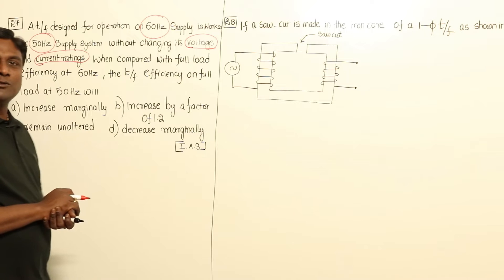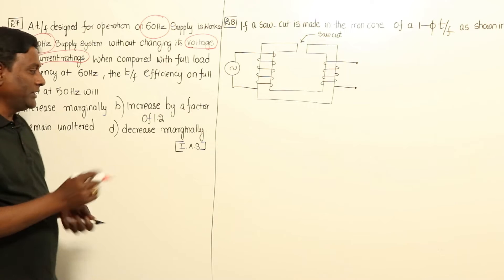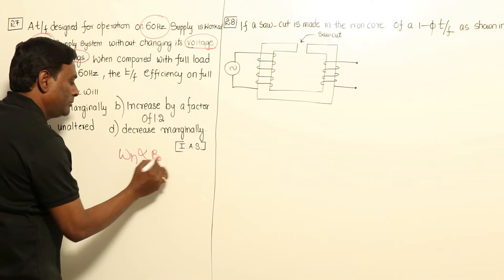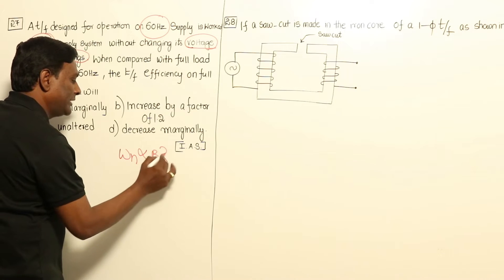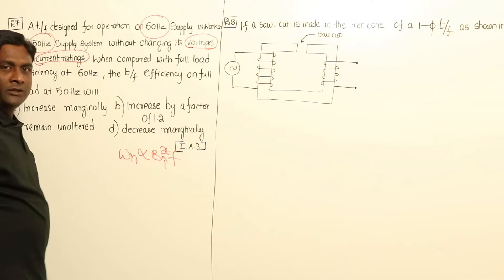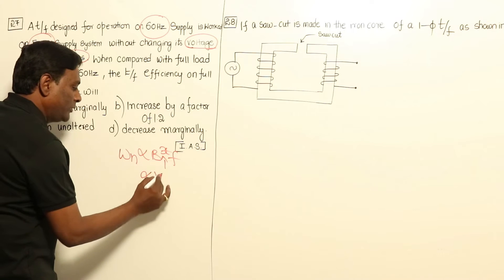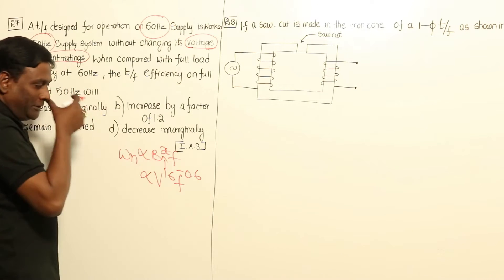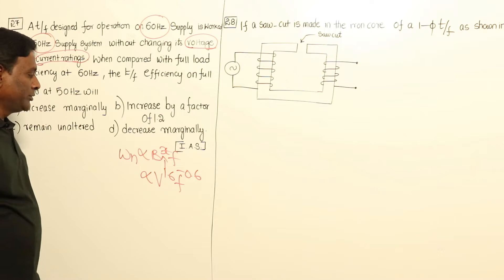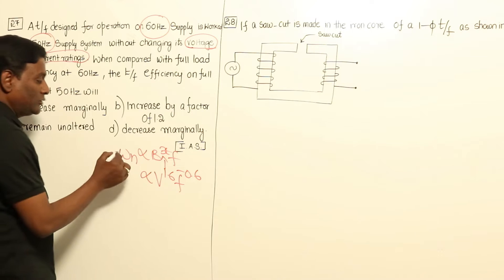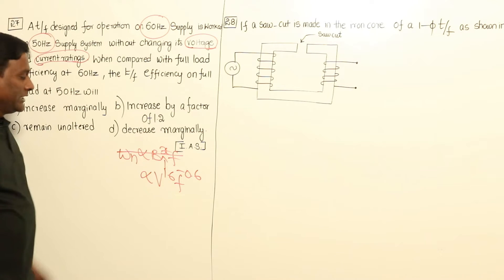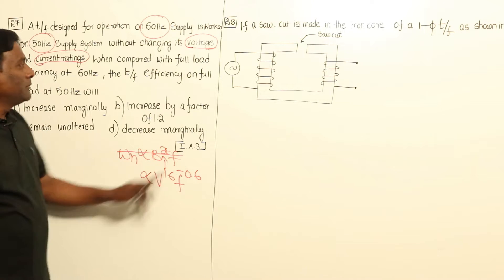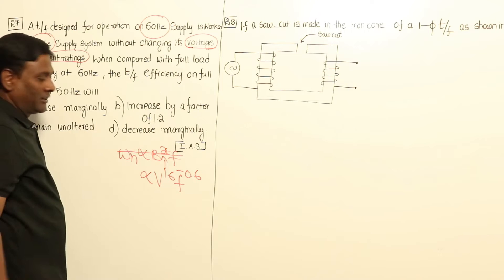The only deciding factor is going to be hysteresis loss. Hysteresis loss is directly proportional to Bmax to the power of X into F, or directly proportional to V to the power of 1.6 times F to the power of minus 0.6. Which equation has to be used? If Bmax is maintained constant, hysteresis loss is directly proportional to frequency. But here, voltages are maintained constant.